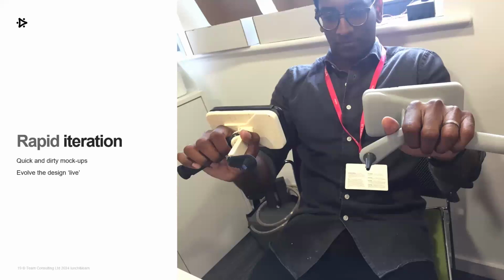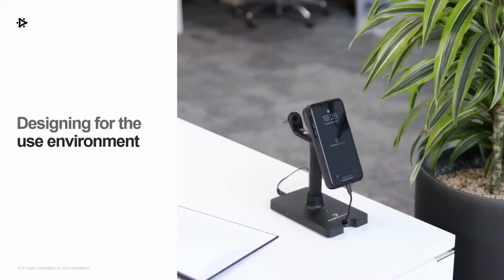So, for example, some of his colleagues reported that the weight of the phone was causing wrist strain. So we quickly went into the workshop and mocked up some phone models where we could experiment with moving the weight of the phone closer to the hand. And we also added a hinged handle to accommodate left and right-handed users. And on the next slide, you can see another design change that came after more formal user evaluation. So the need for a light was highlighted by the users so that they could get better imaging of the ear.